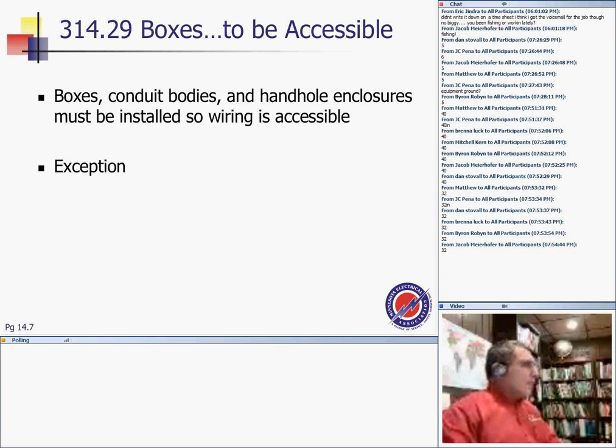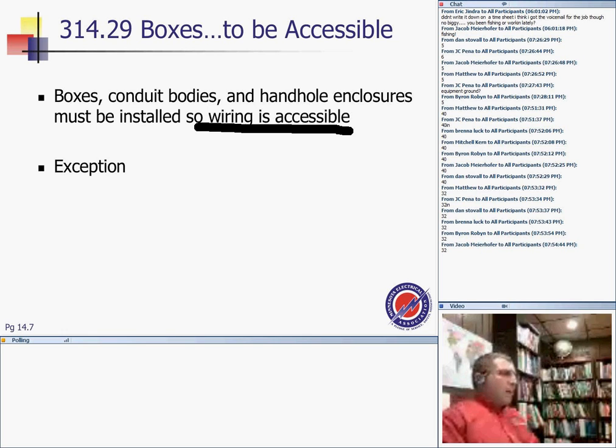Okay, boxes to be accessible. Boxes, conduit bodies, and handhole enclosures must be installed so the wiring is accessible. You can't cover sheetrock over a J box or a pull box or a device box, because they have to be accessible. You've probably seen, guys, a lot of troubleshooting. I don't know how many of you have been in a place where you troubleshoot, trying to figure out what's going on, only to discover that there's a J box that has been sheetrocked over. There's no way you can troubleshoot a circuit if you don't know where the J boxes are located. So these have to be accessible.